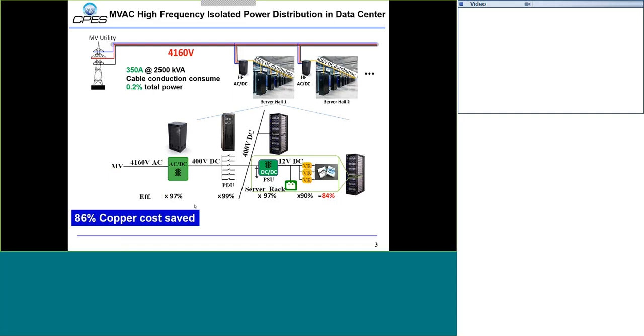We can also save copper on the DC line because we only need around 350 amps on this high-voltage AC-DC line. So you can also save the copper cost. In this proposed architecture, one of the key technologies is this high-frequency AC-DC converter.